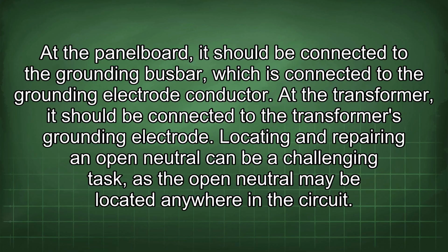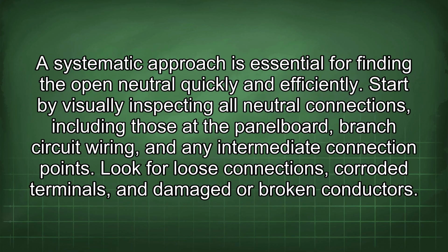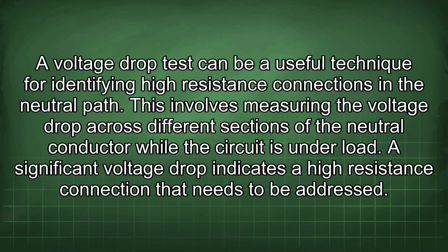Locating and repairing an open neutral can be a challenging task, as the open neutral may be located anywhere in the circuit. A systematic approach is essential for finding the open neutral quickly and efficiently. Start by visually inspecting all neutral connections, including those at the panel board, branch circuit wiring, and any intermediate connection points. Look for loose connections, corroded terminals, and damaged or broken conductors. A voltage drop test can be a useful technique for identifying high resistance connections in the neutral path. This involves measuring the voltage drop across different sections of the neutral conductor while the circuit is under load. A significant voltage drop indicates a high resistance connection that needs to be addressed.